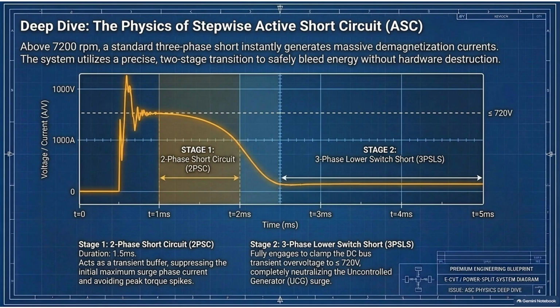That's why it is explicitly stepwise. How does that work? The safety controller shorts only 2 of the 3 phases for precisely 1.5 milliseconds. Oh, so leaving that third phase open momentarily throttles the initial surge. Exactly. It acts as an inductive buffer to suppress the peak transient torque. It's essentially slipping the clutch electronically to bleed off the initial shockwave. That's a great way to visualize it.